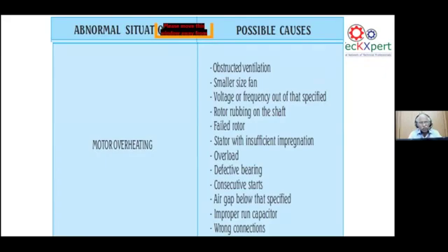So is the air gap specified by the OEM maintained? If it is a single phase motor, an improper run capacitor can also raise the temperature of the motor. So motor overheating has almost 10 or 12 factors, which are all the areas causing the overheating that can be addressed as such.